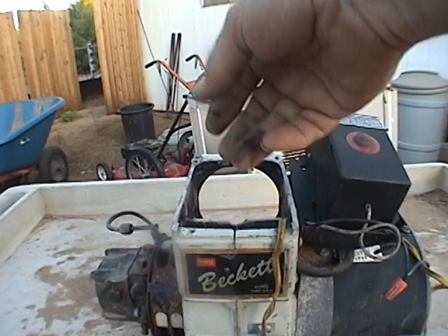It's a 45-second delay that you don't need. It works with a fire eye, basically tells the control whether or not you have flame, and if you don't have flame, shuts it off. But you'll just discard this, and you'll put your switch, or you'll put your timer right in this spot. So this is how it starts. That's how it starts, pretty much.